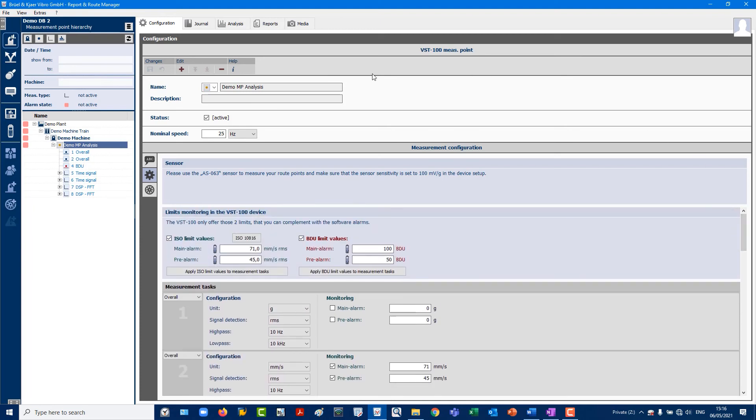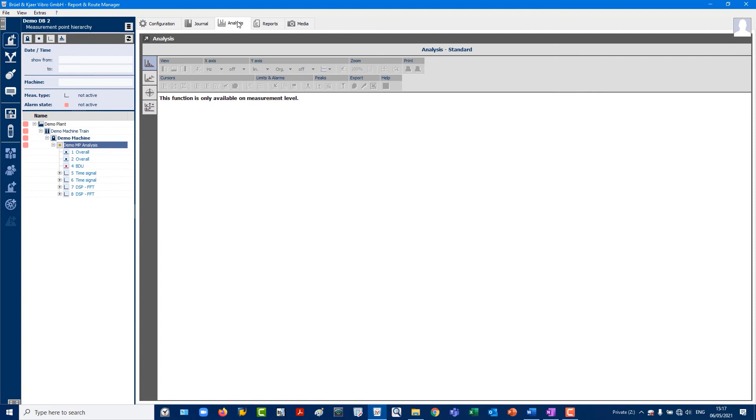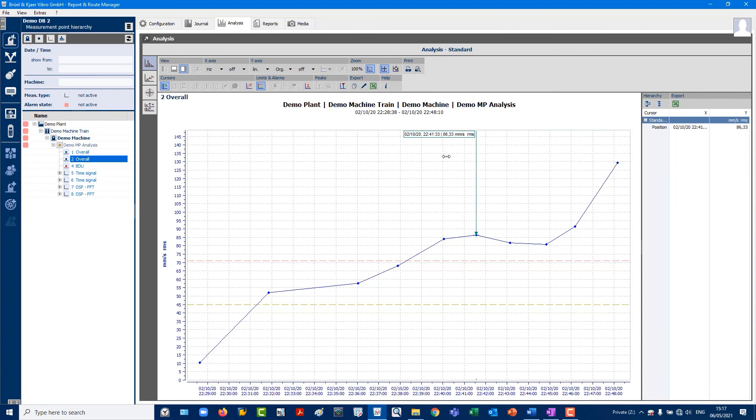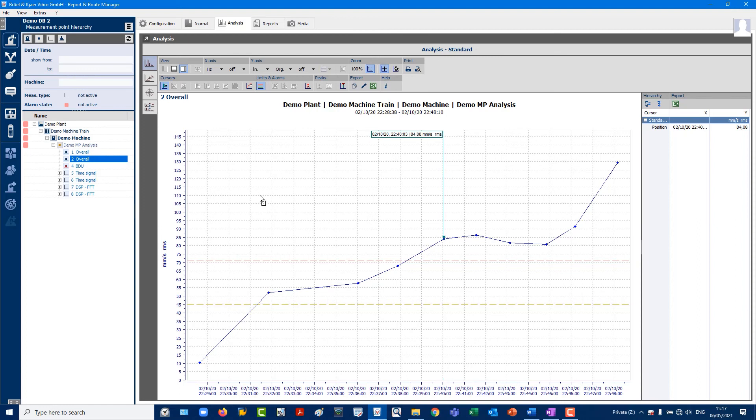Switch to the Analysis tab in the top center. First, let's look at the overall trend of Task 2, which has increased over time and, as indicated by the cursor, triggered the red alert on the 2nd of October 2020 at 10:40 PM. The red alarm has already been checked during uploading and will be indicated by red marking in the plant hierarchy.